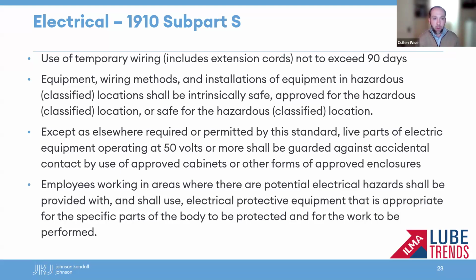All right, and then these last 2 bullet points, now we're circling back to NFPA 70E requirements or standards. So except as elsewhere required or permitted by the standard, live parts of electric equipment operating at 50 volts or more have to be guarded against accidental contact by use of approved cabinets or other forms of approved enclosures. So the standard, in another area, goes on to say that if that cannot be met, and there's really an anticipated exposure to live parts of electric equipment at 50 volts or more, this is when we have to really take a look at NFPA 70E and meet the requirements within 70E specifically, and most notably probably is training for personnel.